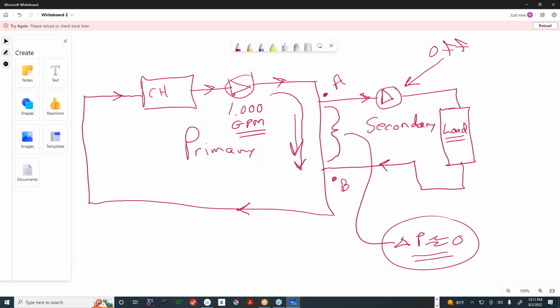And as long as that pressure drop is approximately equal to 0, that means there will not be any flow induced in the secondary circuit. Now, in the world of piping, there's no such thing as zero pressure drop, but it is very, very close. And the whole idea when you design a primary secondary loop and you design a bridge is to make that pressure drop negligible or as close to 0 as possible. And that way, there will be no flow directed into the secondary circuit. So far, so good. Anybody have any questions about that basic concept of the zero pressure bypass?